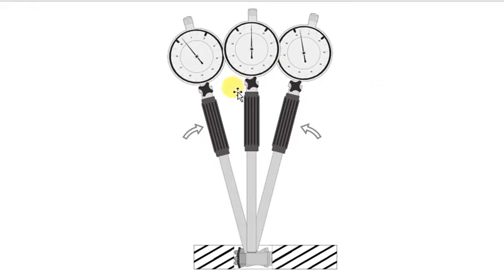There are three points to measure using bore gauge. I mean there are three points to make sure of your measurement. First one is the more the gauge head is inclined, the smaller the displayed value. That is, if the inclination of the dial gauge indicator is more, then the value in this reading increases.